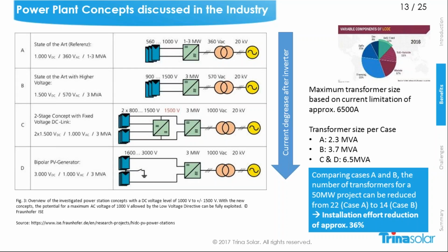Why can it be important? If you take now a look at the transformer, the transformer usually is limited, based on the information I got from a manufacturer, on the current. The limit is at a current of approximately 6,500 amperes. If we now calculate the maximum size per case, then in case A, with an input voltage of 360 volt AC and an output voltage of 20 kilovolts, we end up at a size of 2.3 megavolt ampere. In case B, with an input voltage of 570, we end up at a size of 3.7 megavolt ampere, and for C and D it's 6.5.